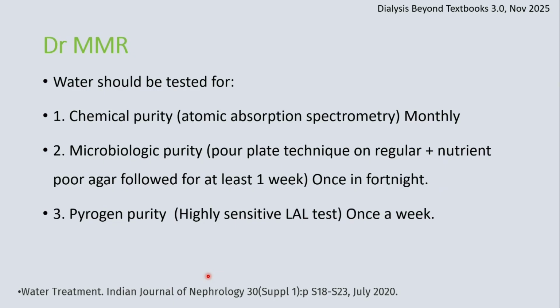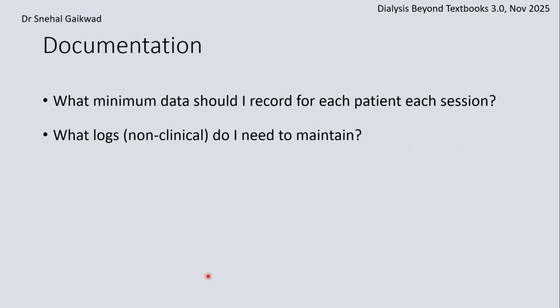For water, you take a sample after your treatment, immediately before the tank, immediately after the tank, and at each dialysis outlet. And about endotoxin? Endotoxin. Okay. And if HDF, then you take the HDF infusate fluid and test it, as I said, at 0.01. I'll add just 2 points to this. Also at the return line, yes, and after the bicarbonate mixer also should be tested.